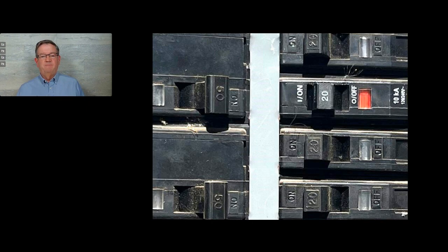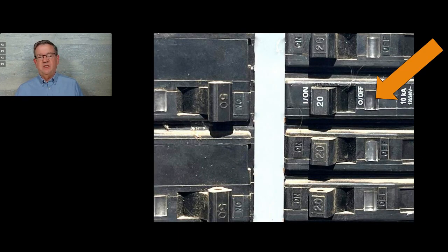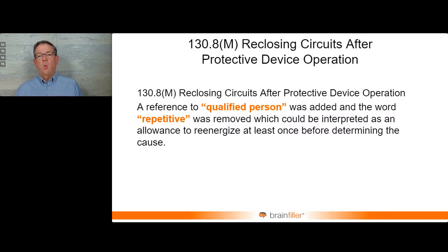Uh-oh. What do you do when the lights go out? Well, you may decide, hey, a circuit breaker tripped. Okay. What do you do when a circuit breaker trips? Well, you identify which one it is, and what many will do is just reset the circuit breaker. Simple enough. Well, no, not according to the world of NFPA 70E. In NFPA 70E, you don't just arbitrarily reset the circuit breaker. You have to identify, why did it trip?